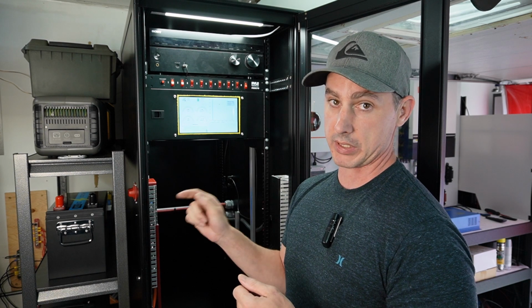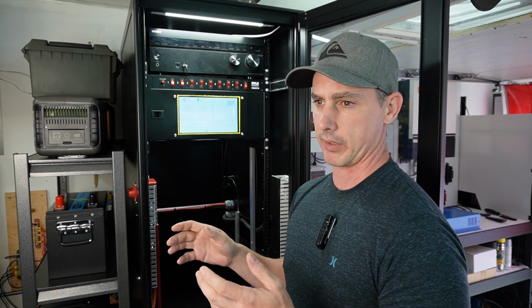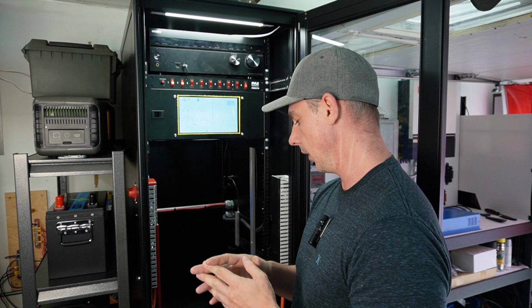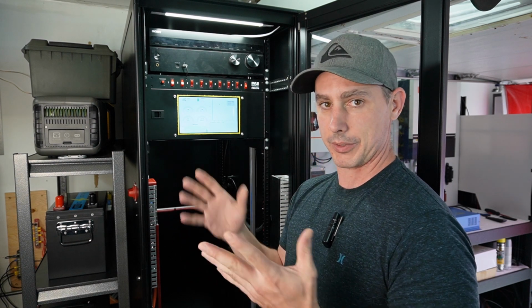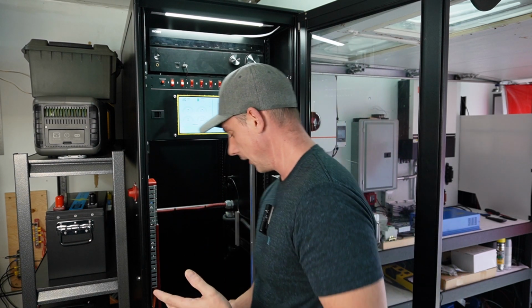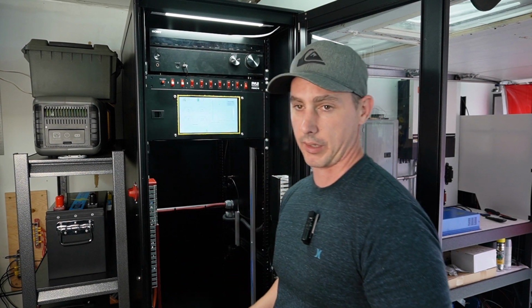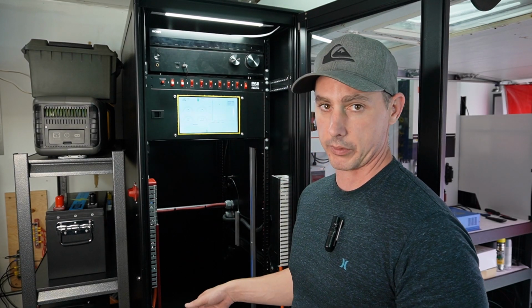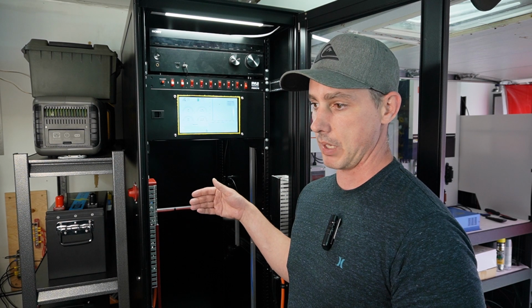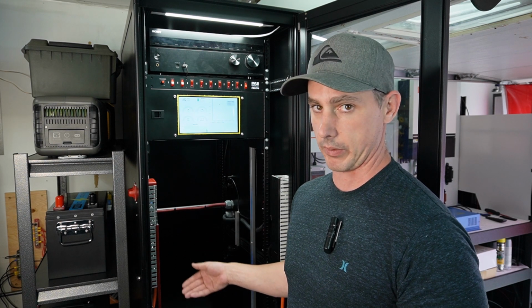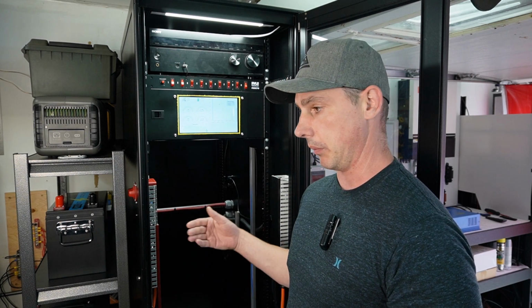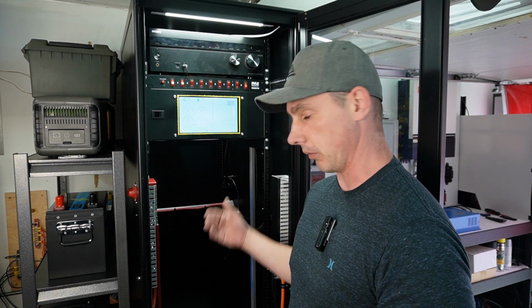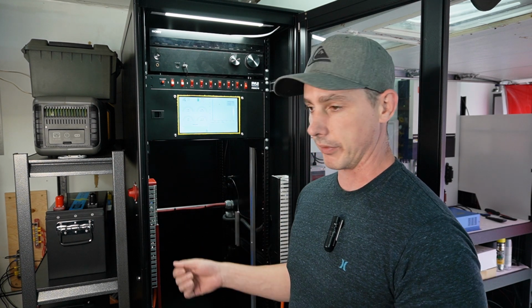So immediately I grabbed my multimeter and I started poking around and I went from positive to case and I was getting the full voltage, like 55 volts or 56 volts at the time. And I was, what's going on here? So I had disconnected, I went through, I thought maybe it was coming through a battery. I was thinking maybe that the case of the battery was ground to the negative and bonded. So I went through all the batteries, couldn't figure it out.